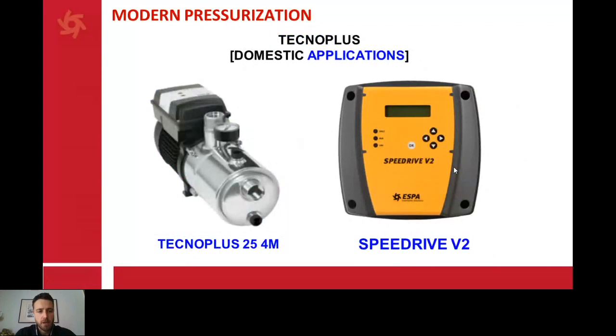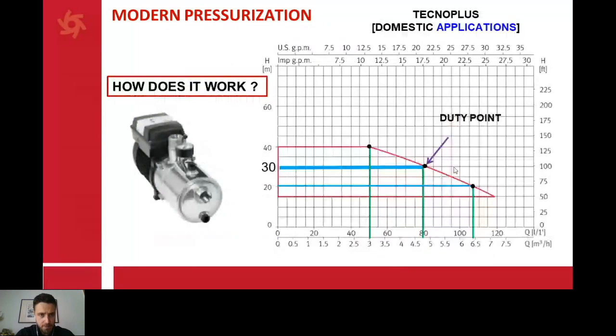And to finish this webinar, we talk a little bit about Tecnoplus, which mounts the same application with the same Speedrive technology. And how does it work? This pump is domestic, but it goes up to 7 cubic meters per hour. And this is the duty point that we have, 3 bar. In case we want 4 bar, we can go up to 3 cubic meters per hour. In case we want 5 cubic meters per hour, we can have up to 3 bar. And in case we want 7 cubic meters per hour, we will reach 2 bar.